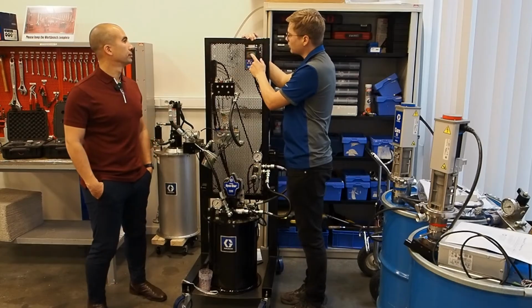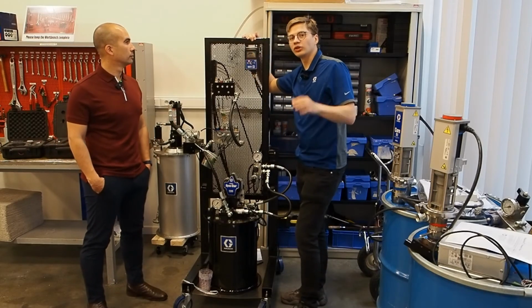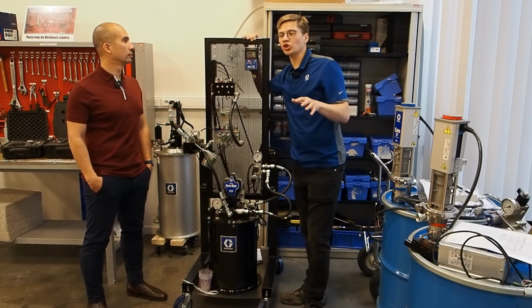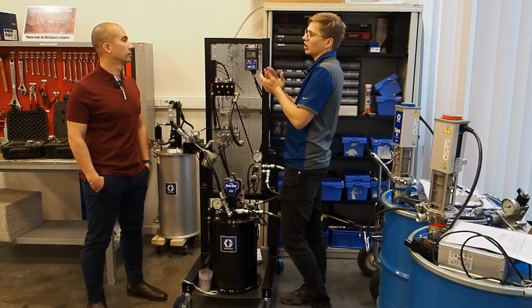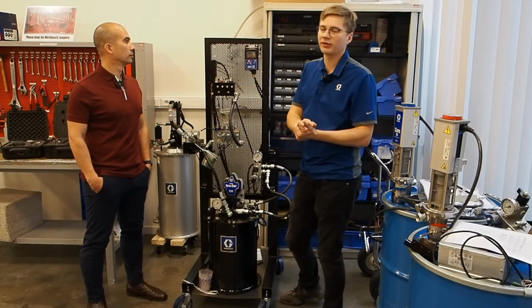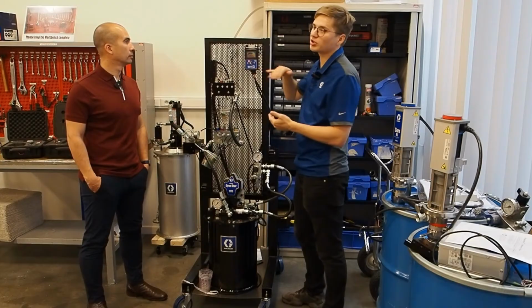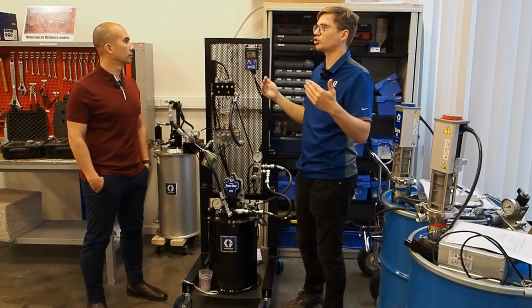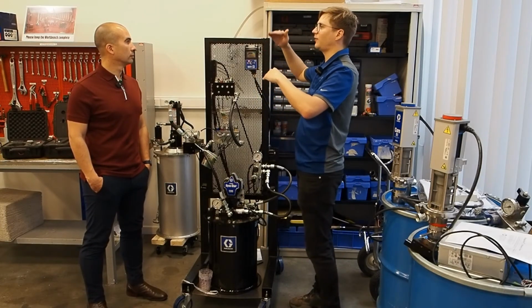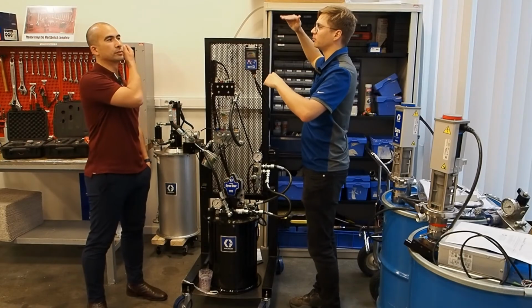And also, if I start the system, you will be able to see here what the current pressure in the system is. So it's not only the pressure switch which reaches the high pressure and tells the pump to stop and opens the vent line. It actually tells you how the pressure is being built up, because I've seen in field troubleshooting that the pressure may start at 50 bar and now it's going beyond that.